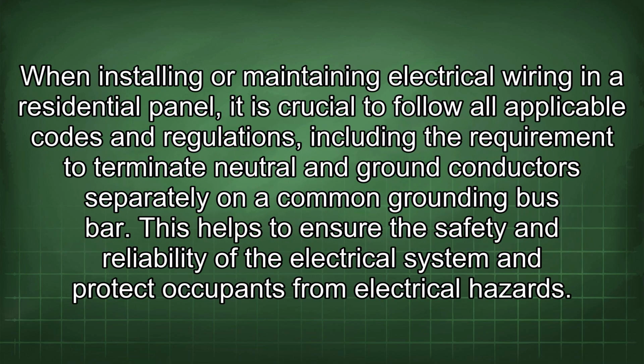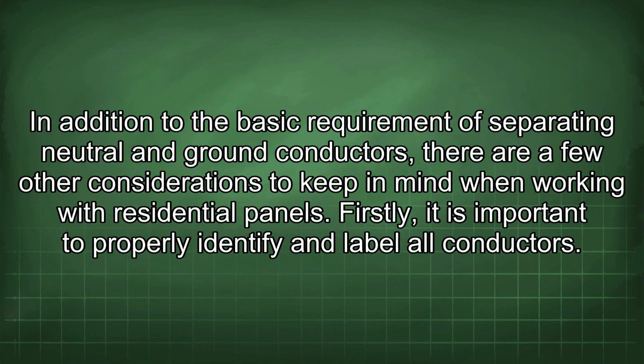When installing or maintaining electrical wiring in a residential panel, it is crucial to follow all applicable codes and regulations, including the requirement to terminate neutral and ground conductors separately on a common grounding bus bar. This helps to ensure the safety and reliability of the electrical system and protects occupants from electrical hazards. In addition to the basic requirement of separating neutral and ground conductors, there are a few other considerations to keep in mind when working with residential panels.